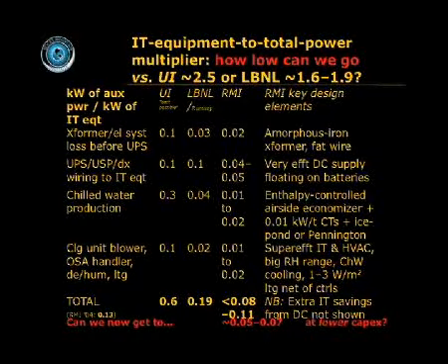So how low can we go? Let's look at how many kilowatts of auxiliary power, that is for cooling, air handling, and power supply, we need for each kilowatt of IT equipment. The Uptime Institute said that when you add up all the overheads, the best you can do is about a 60% overhead on top of the IT use.